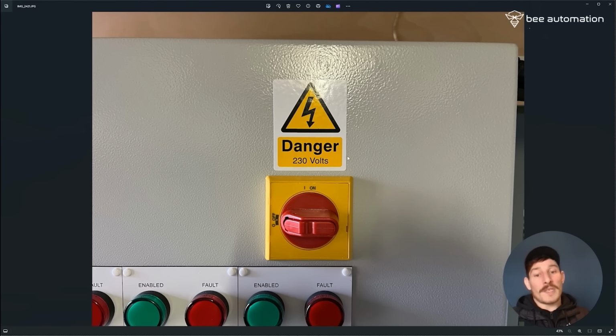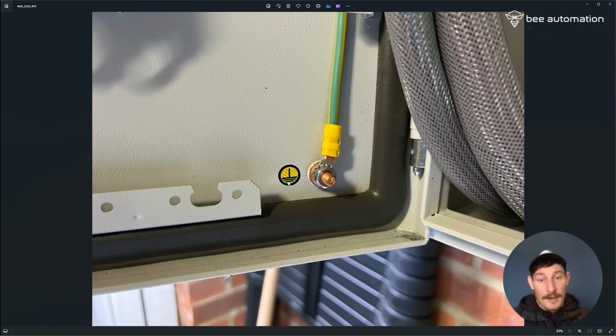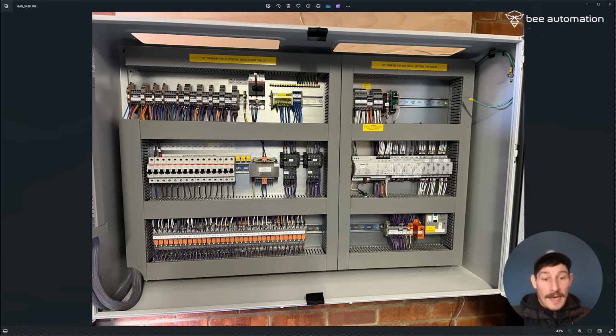Whatever the voltage is of your panel, in this case it's a 230 volt panel but it might be a 410 in your case, just make sure you put this danger voltage label on the front of your panel matching that voltage, and also mark the bonding points, the earth points. That's basically it for the labeling.